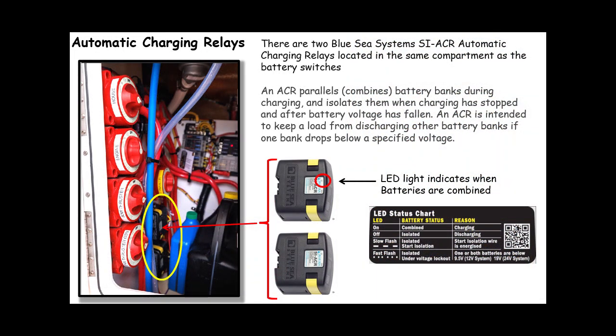In the same compartment as the battery switches are two automatic charging relays, designed to combine battery banks, say the house and the engine, while charging is occurring. When charging stops, it disconnects those banks, so that if one particular battery goes bad, it can't affect the others. There's an LED light on each of the ACRs that indicates battery status. Green means they're all combined and working as intended during the charging process.